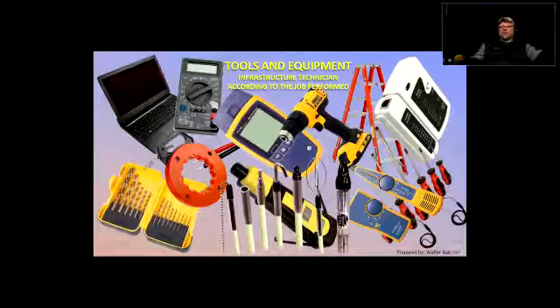a certifier, okay? And a certifier goes through way more rigorous tests such as frequency response, crosstalk, attenuation, and many other aspects, just to make sure that the link fulfills the specifications of Cat5e or Cat6 or Cat6a or whatnot.